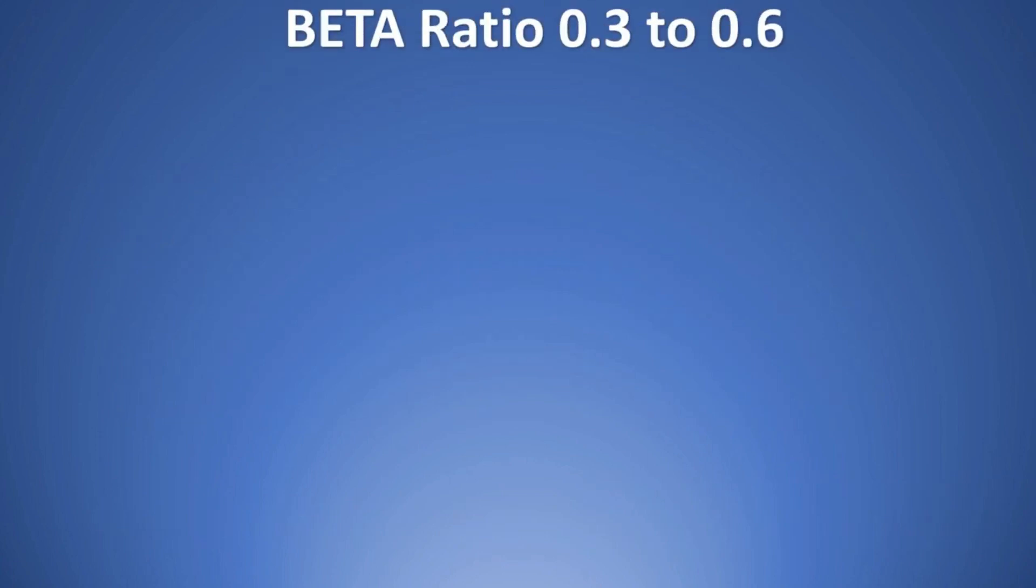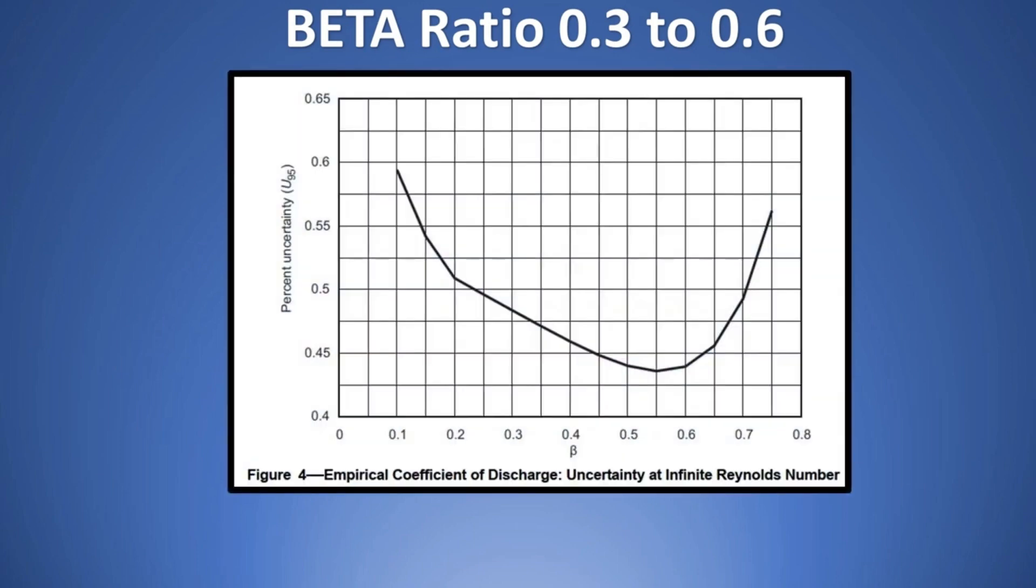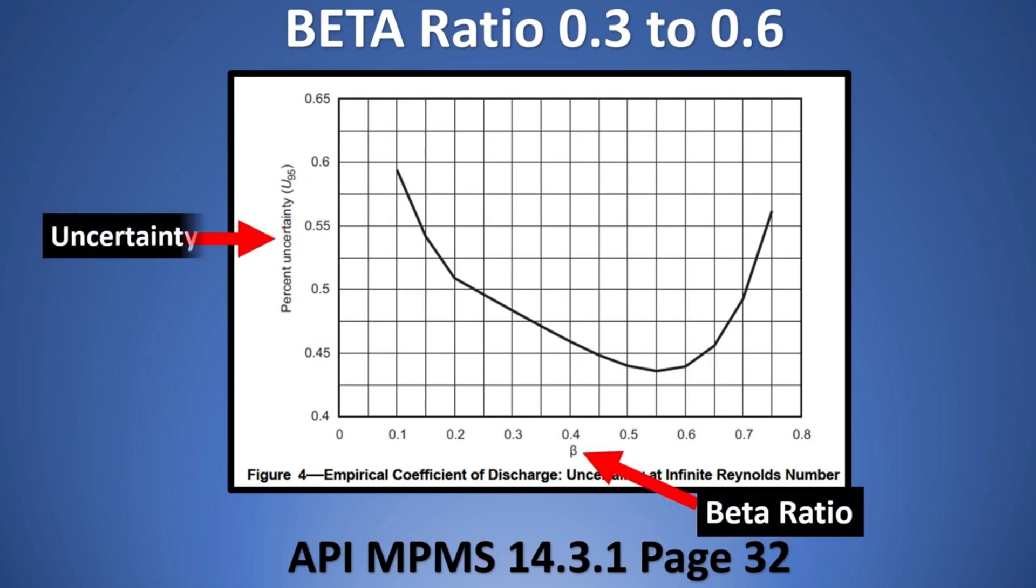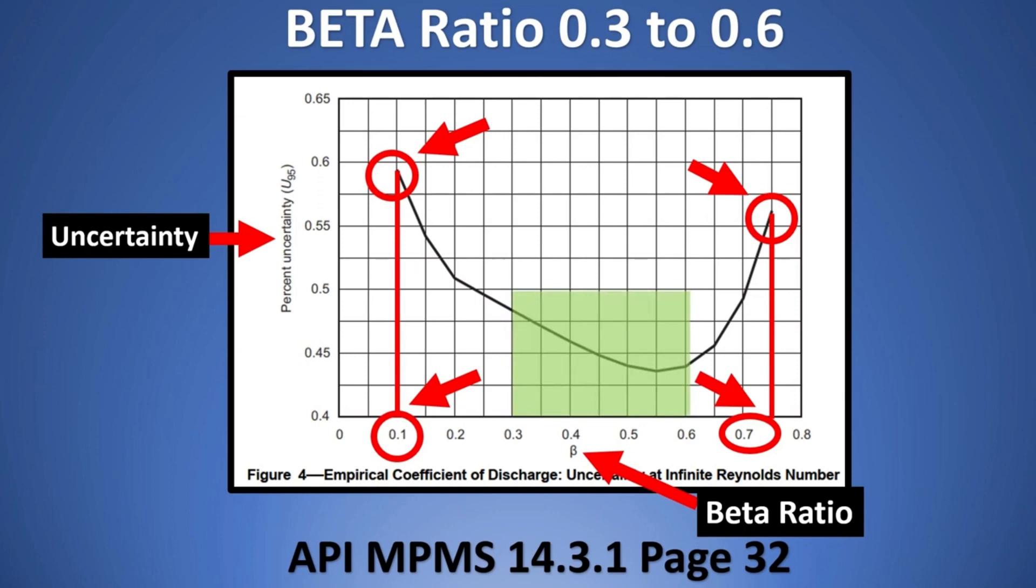But why do I personally love this and I would recommend you to read this standard is because if you see here, for example, I have made a video saying that when is the beta ratio between 0.3 to 0.6, etc. If you see here in this chart, this chart is taken from API MPMS standard. The x-axis you will have is beta ratio and on the y-axis you are going to have the percentage uncertainty. Now if you see at very extreme ends which is 0.1 or 0.7 of beta ratio, if you see the uncertainty, it is too high. If you see here, if you keep the beta ratio as 0.1, the uncertainty could go up till 0.60%. But if you see in the middle range between 0.3 to 0.6, here the uncertainty is far less. If you see the graph is going down. We usually, that is why I recommend to keep the beta ratio between a middle range. Such insightful information is available in these API MPMS standards.